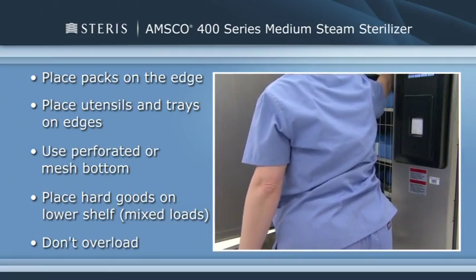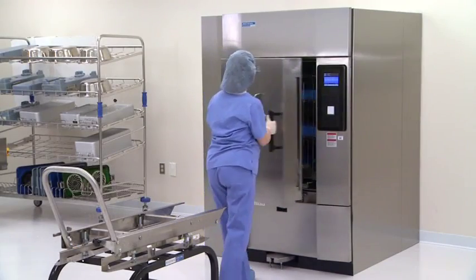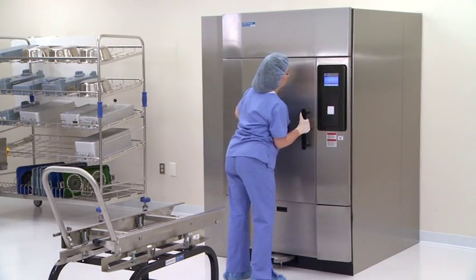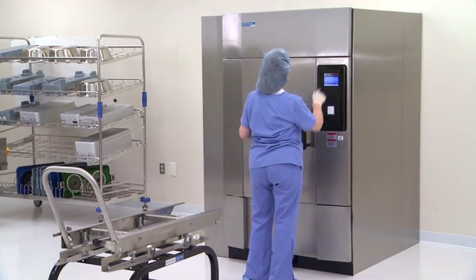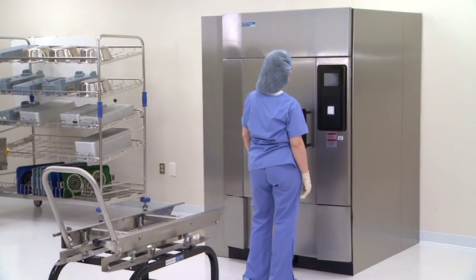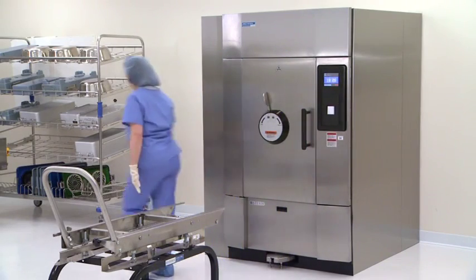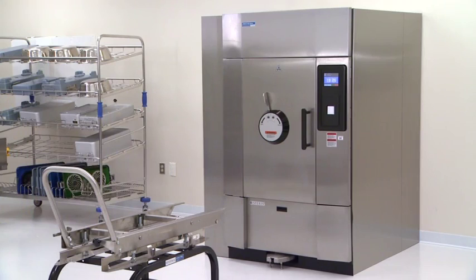After placing the load in the chamber, close the chamber door. The sterilizer is now ready to run a cycle. Materials capable of holding water, such as solid bottom pans, basins, and trays, should be positioned so that they're oriented in the same direction and so that condensate can be eliminated.